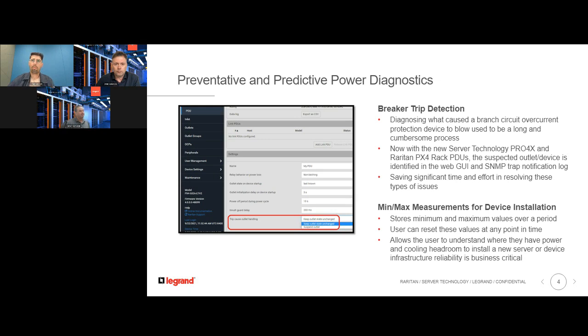Secondarily, one of the other problems that's fairly common within the industry is deciding where to install a new device. So I've got a new server, and I need to know where to put it. I really need three things. I certainly need to know that there's cooling available, I need to know that there's power available, and obviously you need to look at U space as well. But that can be a very daunting, sometimes manual process.